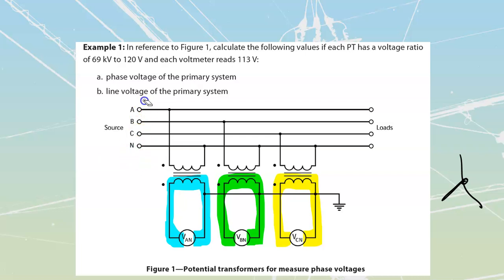It says calculate the following values if each PT has a voltage ratio of 69 kV to 120 volts and if each voltmeter reads 113 volts. So if I have a 69 kV to 120, that's going to be my ratio over there. Now I can simplify this down into a smaller, simpler ratio if I want, or I can work with the 69 over 120. We're going to work with the 69 over 120. If I take a look at what my voltmeters are actually reading, they're not reading 120, they're reading 113.